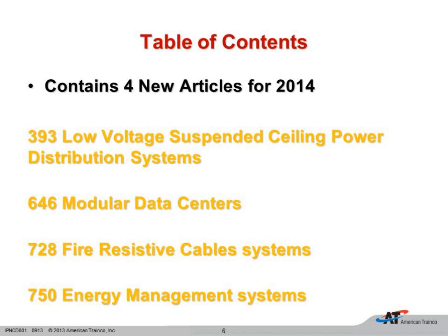The next article we see, modular data centers. So for a long time in the code we've had Article 645, IT equipment, but it really didn't address when the data center was built off-site and then delivered as one unit. So this is a prefabricated unit. It is 600 volts or less. It's going to have an outer housing, of course, and inside it will have its racks and cabinets, servers, UPS systems. It will come with its own air conditioning system, so it's a one-shot deal, and it will show up completely wired and ready to go, and all we have to do is supply power to it. So the National Electrical Code wanted to address this to catch up on technology a little bit.